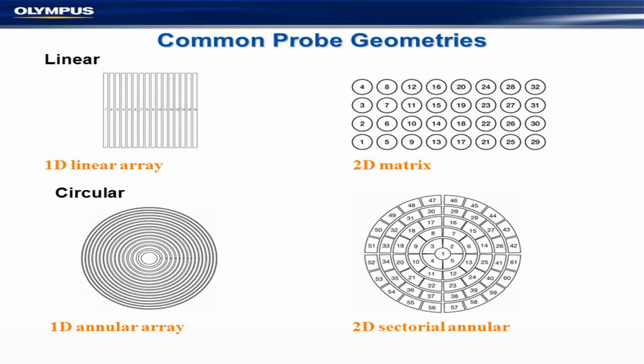There are quite a lot of common probe geometries. 90-odd percent of the probes you'll come across will be linear arrays, for two obvious reasons. The first is there's an awful lot less elements in there, so they are a lot cheaper to buy, and that particularly applies to the instrumentation. The arrays themselves are generally not as expensive as the instrument.